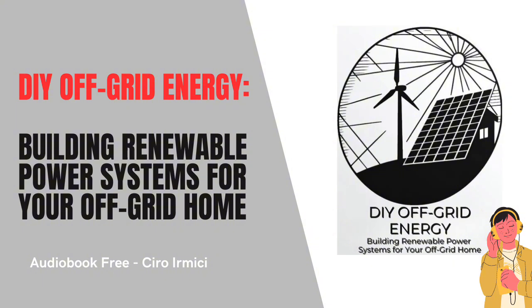Inverter and electrical system maintenance. The inverter and electrical components of your off-grid system are critical to converting and distributing the power generated by your renewable sources. Inverters, charge controllers, and other electrical devices should be regularly checked to ensure they are operating correctly. Dust, moisture, and heat can all impact the performance of these components, making proper ventilation and environmental control important for long-term reliability. Periodic inspections of the inverter include checking for error codes, verifying that it is correctly synchronized with your battery bank and renewable sources, and ensuring that the cooling fans are functioning properly.